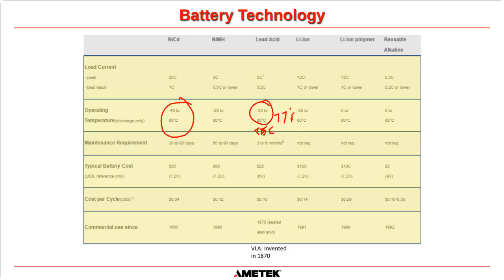But for a lead acid battery, and even for a lithium ion battery, you can see here at this discharge, the negative temperatures are much higher, much closer to zero. But once again, it's the temperatures when they are being charged. And once again, these are also very temperature sensitive. The higher the temperature, the more likely they are to go into thermal runaway. And therefore, they have to have some protection systems in place to stop that from happening.